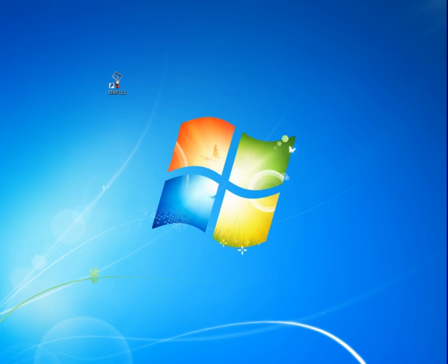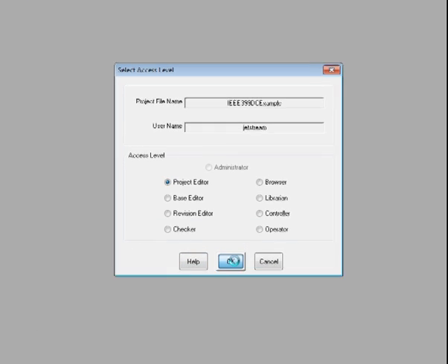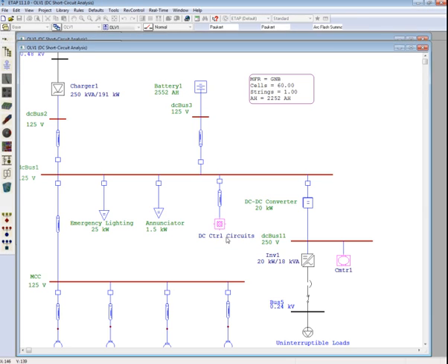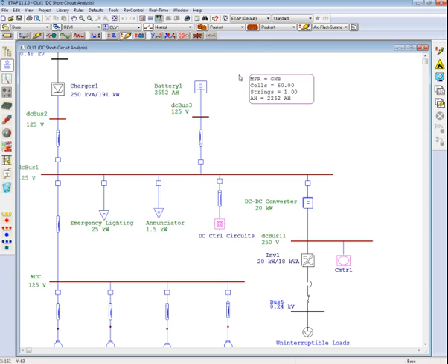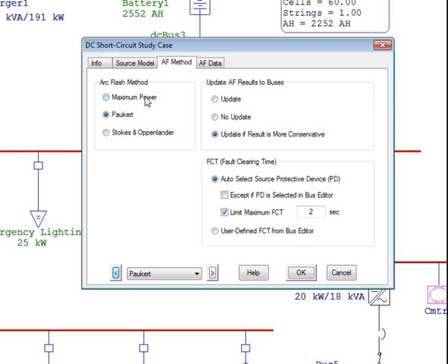Now, let's utilize the maximum power method in ETAP. First, go to the DC system presentation. Once we have opened up the file, we should be able to go to the study case and select the proper methodology. In this case, we will be selecting the maximum power method. This option can be found in the arc flash method tab in the study case.